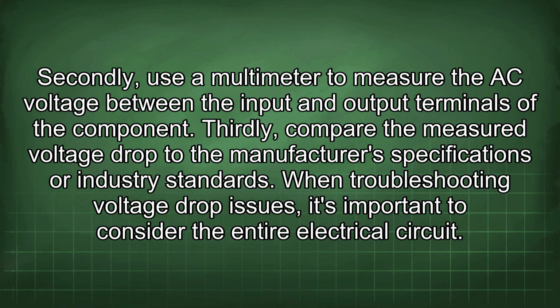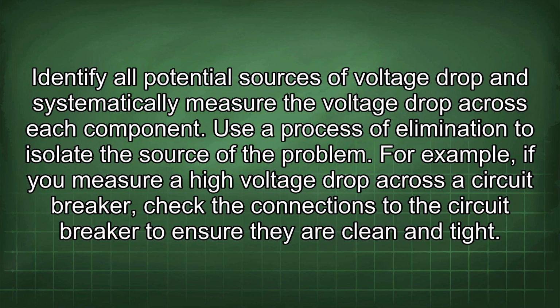When troubleshooting voltage drop issues, it's important to consider the entire electrical circuit. Identify all potential sources of voltage drop and systematically measure the voltage drop across each component. Use a process of elimination to isolate the source of the problem.